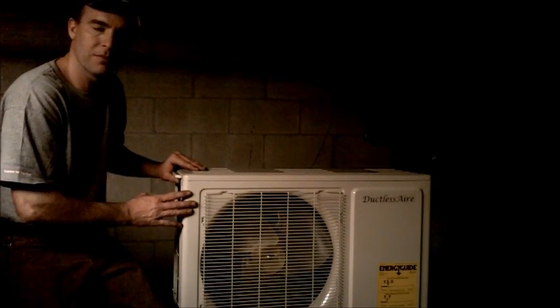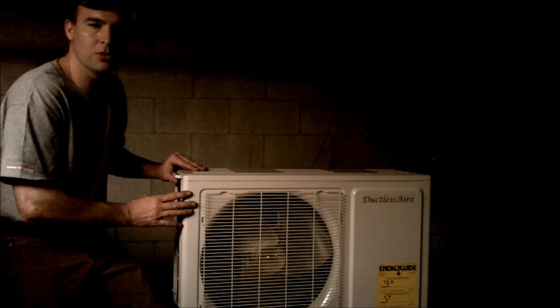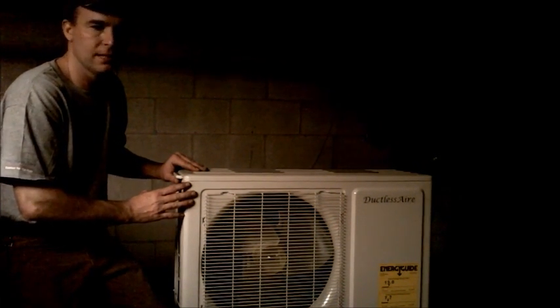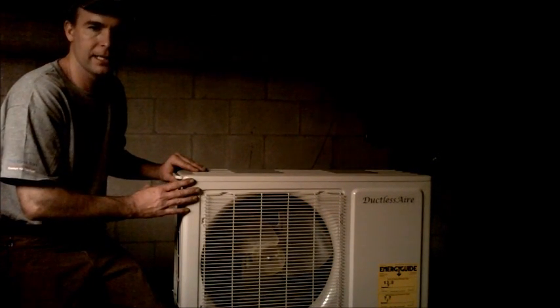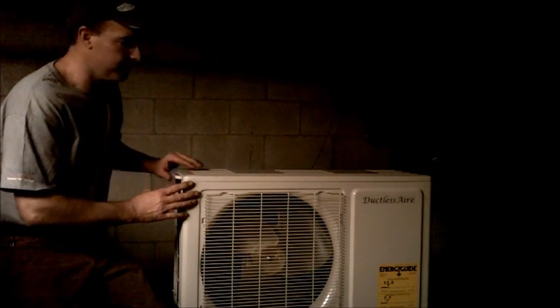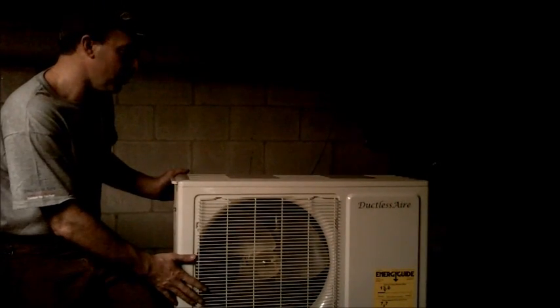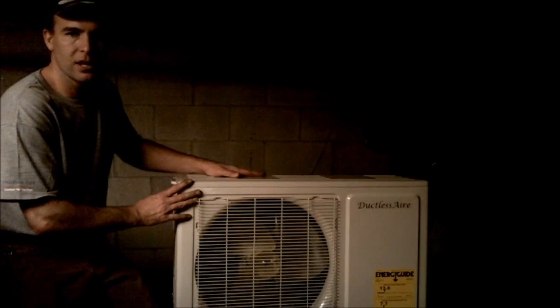Anytime you're above a ceiling, by code most of the time they recommend a secondary pan. If it's outside on a bracket, it really doesn't matter. But above a ceiling, put a pan in and run an auxiliary drain out. So anyway, we're going to start our install. We'll put it up on two blocks, make our connections, and finish our wiring.